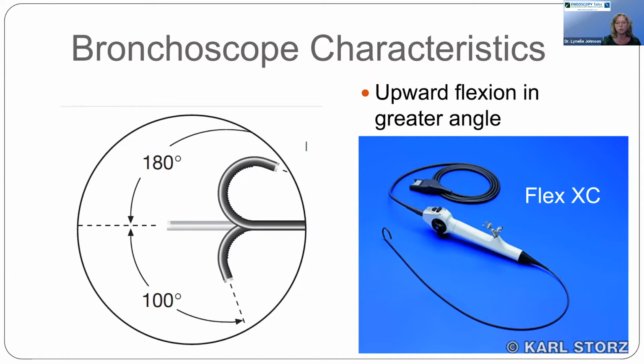One of the things to watch if you are interested in the Flex XC is that it actually has two different handle types. One I call the bronchoscope handle, which is where you push the lever down and the tip goes up. The cystoscope handle, when you push the lever down, the tip actually goes down. So make sure you talk to your Storz representative before you buy one of those scopes so you make sure you get the type that you want. We've had both of them in our hospital, and now we rely primarily on the bronchoscope handle for use.